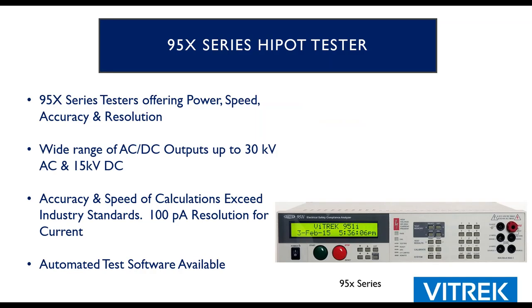All right, and then the other family of testers that we have is the 95X. This particular mainframe is very flexible. We have multiple voltage output options, 6, 11, or 15,000 volts DC, 6 or 10,000 volts AC with an external option up to 30,000 volts. If you need speed and precision, this is definitely the top tester on the market. We're able to do test times in 100 milliseconds or less, depending on voltages there.